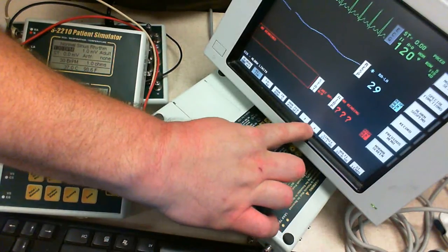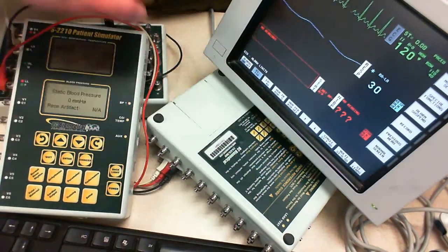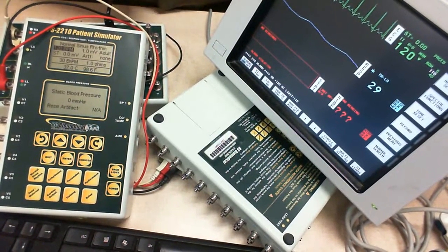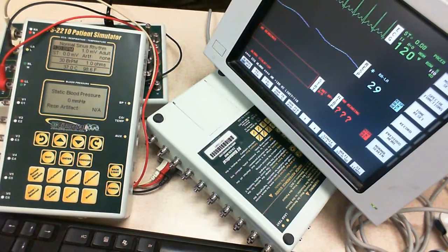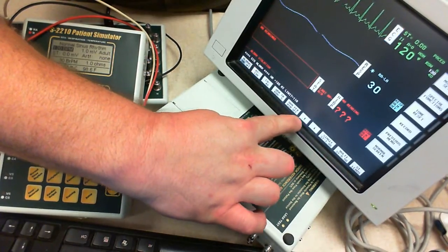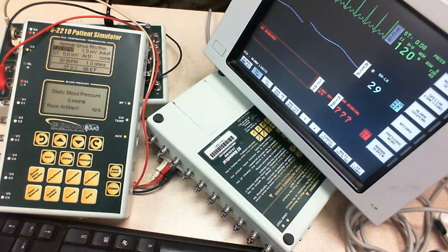Okay, I'm going to drop my alarm slightly. Drop it to 110. There we go. I dropped it to 110. It took less than 10 seconds for it to respond. You do want to have a slight alarm delay. I'm going to go ahead and raise it so that it's not alarming at us constantly. You do want to have a slight alarm delay, and that's actually at the bottom of the check. We'll go ahead and mention more about that.